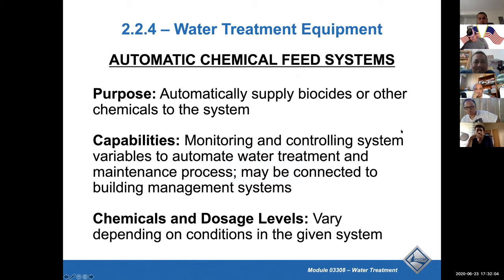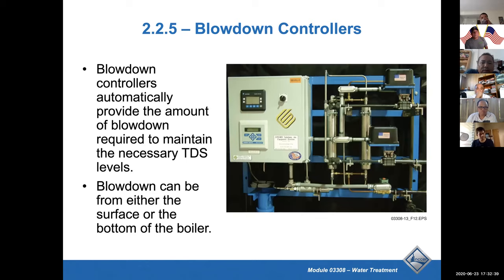Automatic chemical feed systems used on cooling towers. They don't use the automatic one on a closed system, they use a mechanical one. Anything closed system, you just add chemicals to it. But the automatic is for any type of evaporative cooling, like a cooling tower. The only problem with evaporative is you got to blow down the system, right? This is basically an automatic blowdown system for a cooling tower.